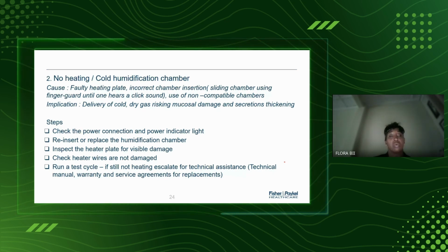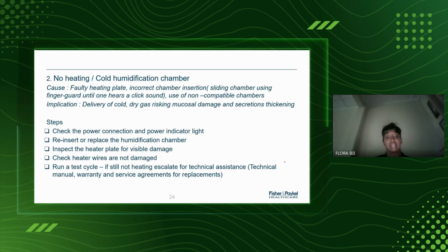In summary, you would check the connection of the power, inspect the heater plate, and I'll show you how it looks, and also check that the heater wires are not damaged. This is a common problem, where you find heater wires that are damaged and might need to be replaced. Then run a test cycle. However, different companies would have different modalities for this, so you would need to check.